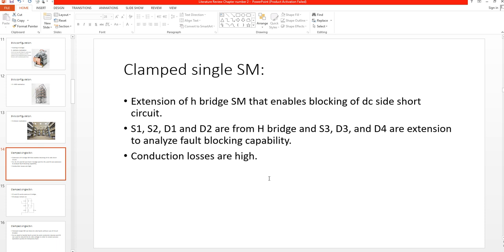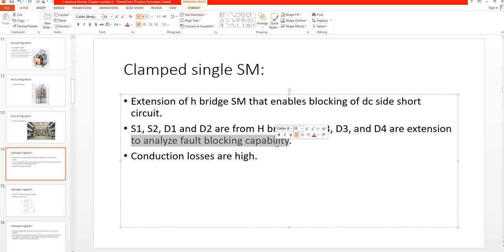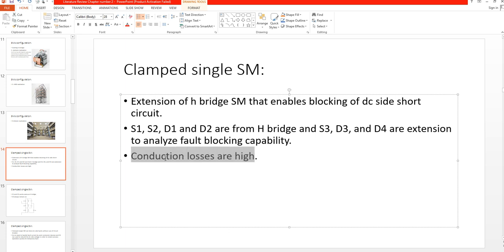To understand the operation of the clamped single submodule: S1, S2, D1, and D2 are taken from the half bridge, while S3, D3, and D4 are the extensions added to analyze the fault blocking capability of this submodule topology. Compared to other topologies, conduction losses are very high because the number of semiconductor devices is increased.